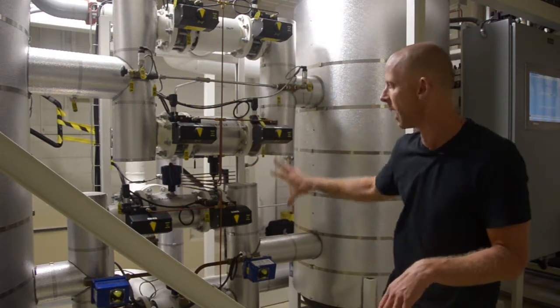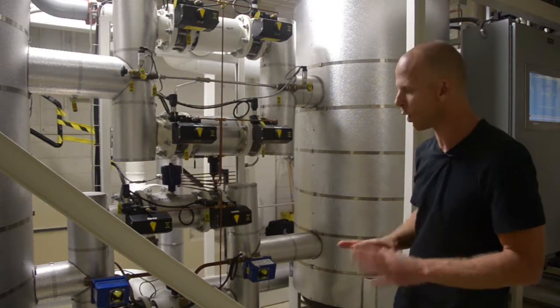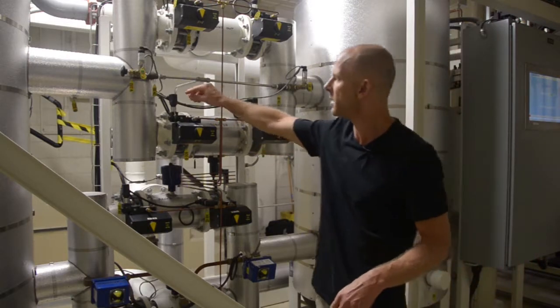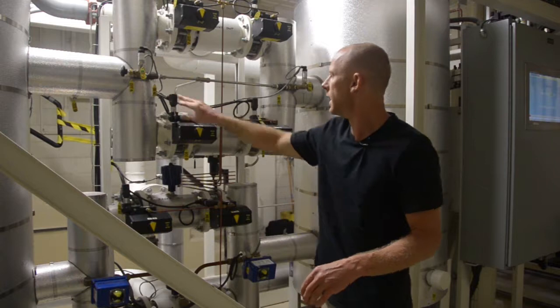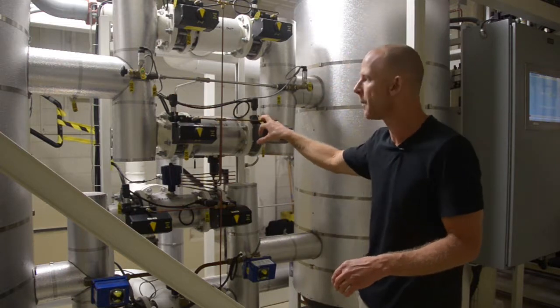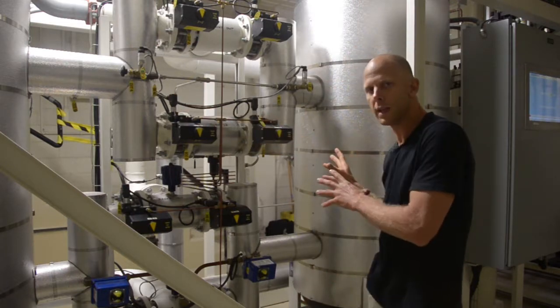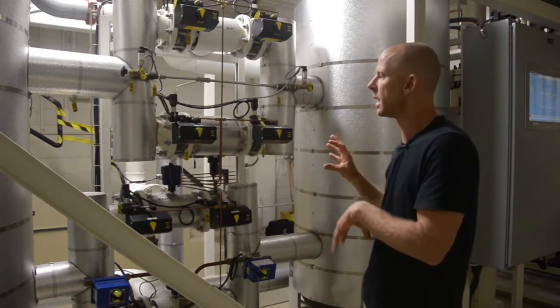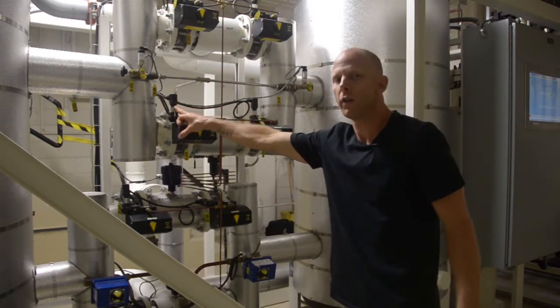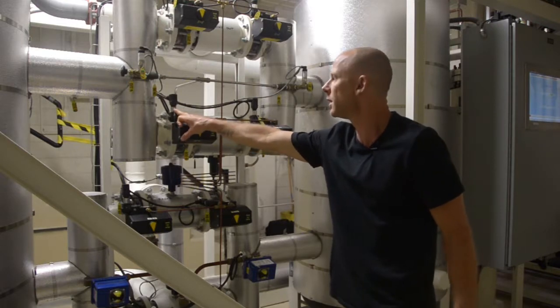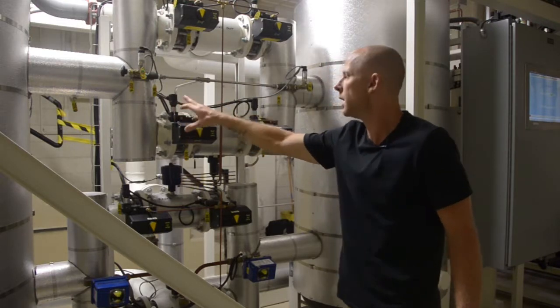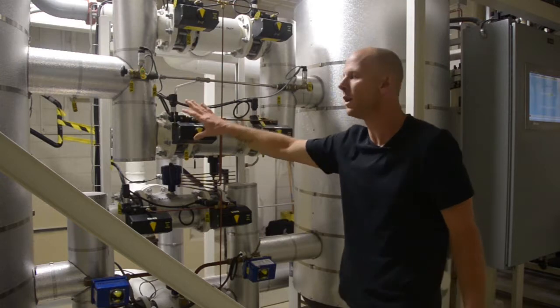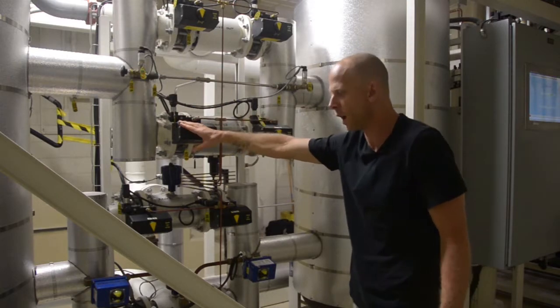These four main valves are all controlled by the PLC. They're automatic valves. You'll see that each one has a solenoid on it and it has an instrument air supply. So the PLC inside our plant computer will basically send a signal to whichever valve needs to be opened. It's a digital signal which will energize the solenoid. The solenoid will allow instrument air into that particular valve and open that valve.